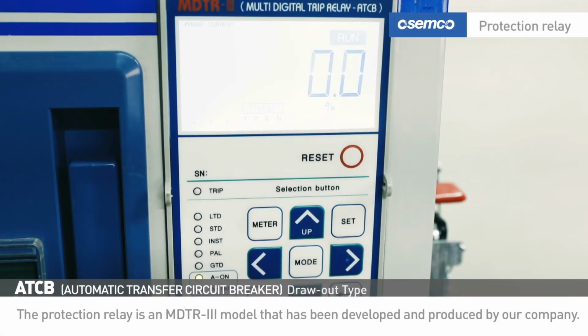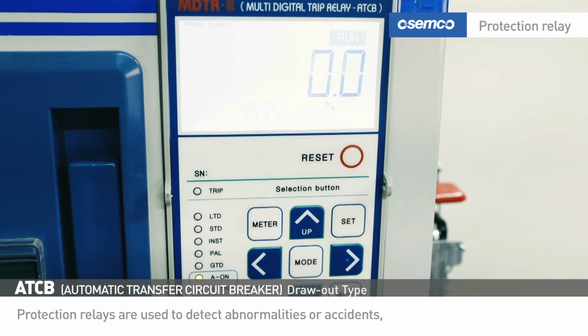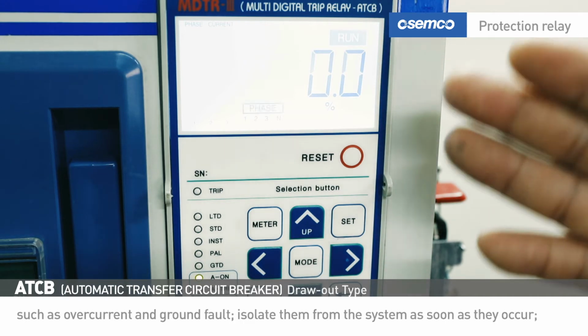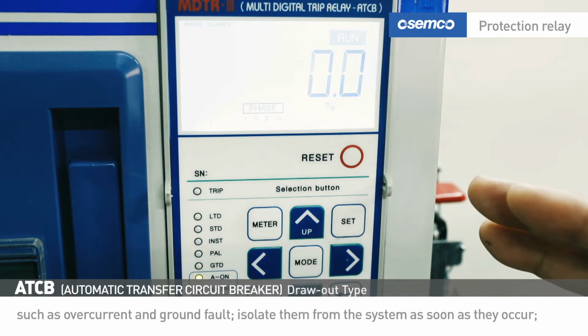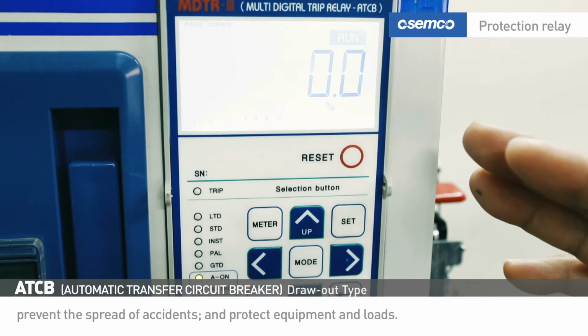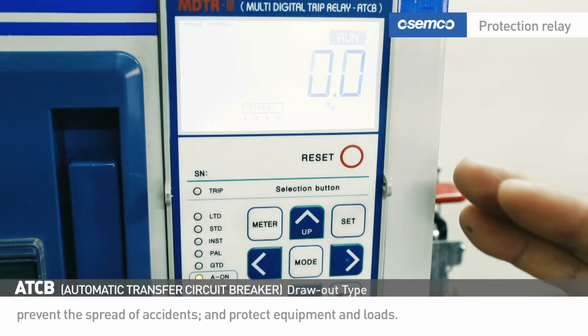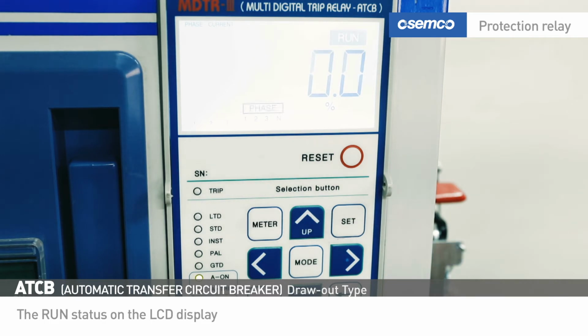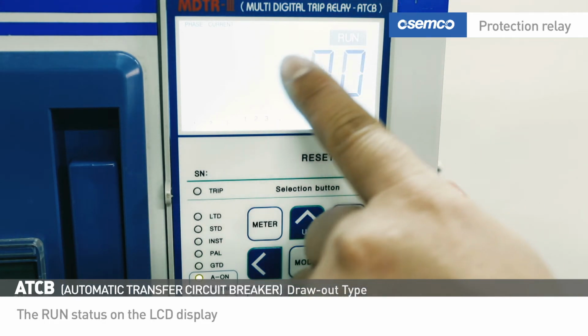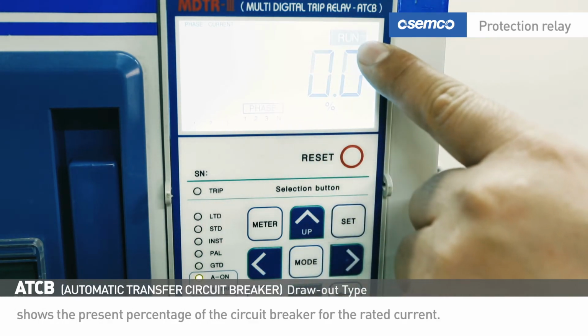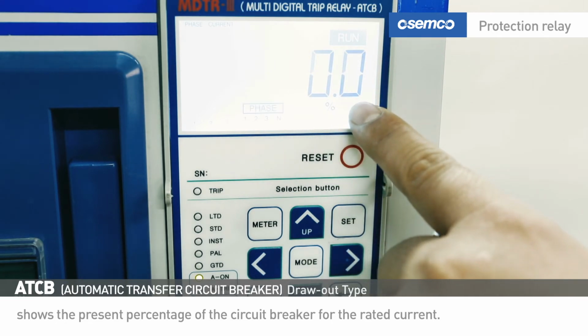The protection relay is an MDTR3 model that has been developed and produced by our company. Protection relays are used to detect abnormalities or accidents, such as overcurrent and ground fault, isolate them from the system as soon as they occur, prevent the spread of accidents, and protect equipment and loads. The run status on the LCD display shows the present percentage of the circuit breaker for the rated current.